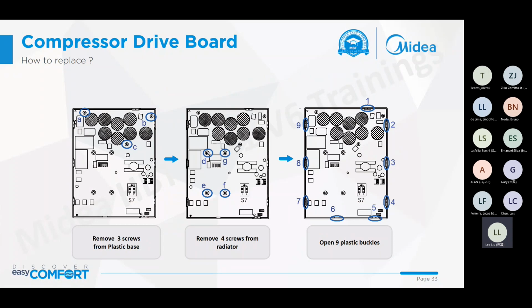Regarding how to replace the compressor drive board, it's not difficult. First, because the compressor drive is inside the box, we need to open the first layer and remove the screws from the plastic base. After that, we also need to remove 4 screws from the radiator. After that, we need to open 9 plastic buckles.